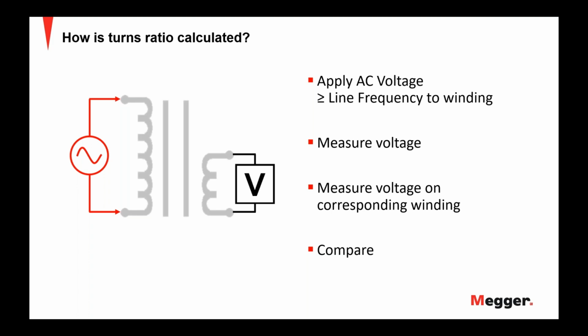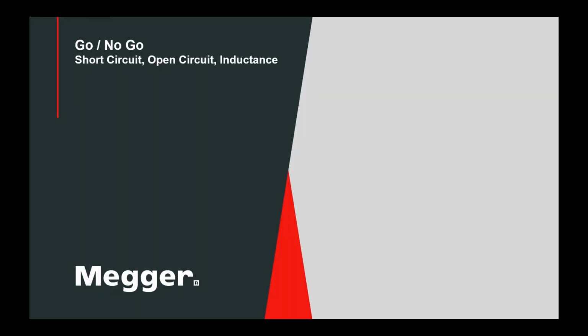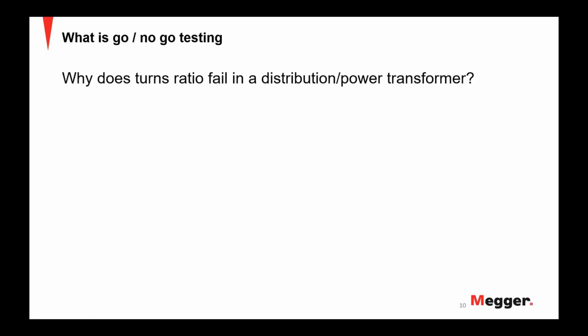So fundamentally, one of the easiest tests to understand when it comes to turns ratio testing, not quite as involved as winding resistance you heard with Yash before. Well, with this device, we saw the opportunity to add in a different test mode, and there are some other instruments on the market today that do this, but this is called the go, no go, where we're looking for short circuits, open circuits, and we're looking for the inductance of that core to be present.